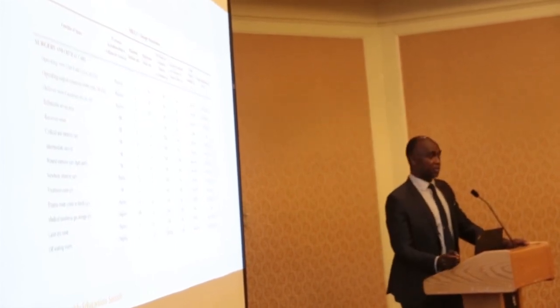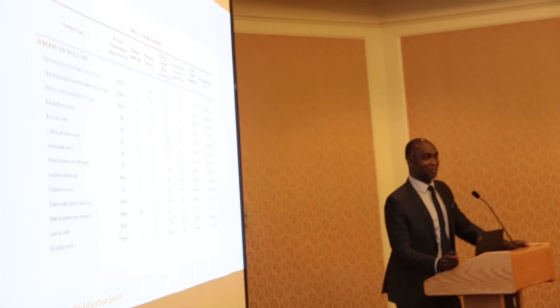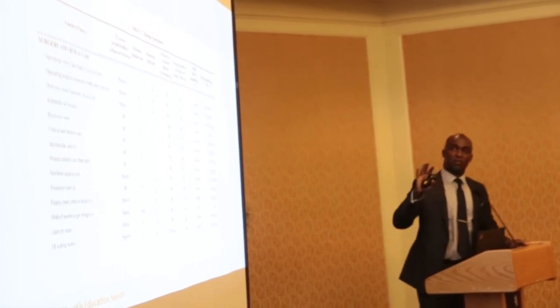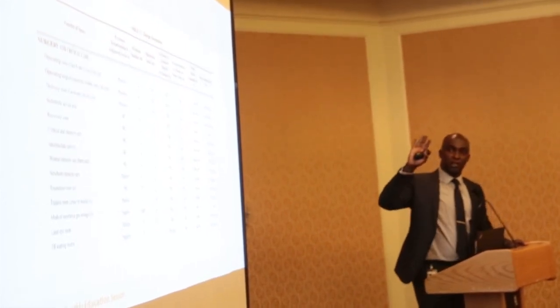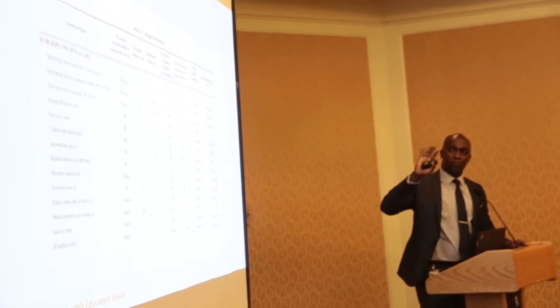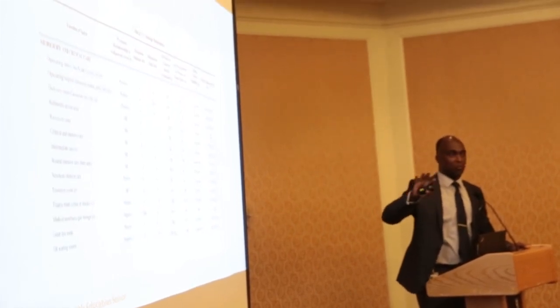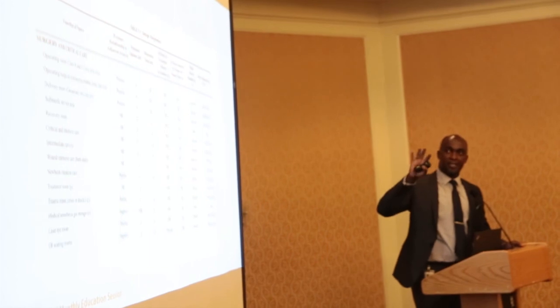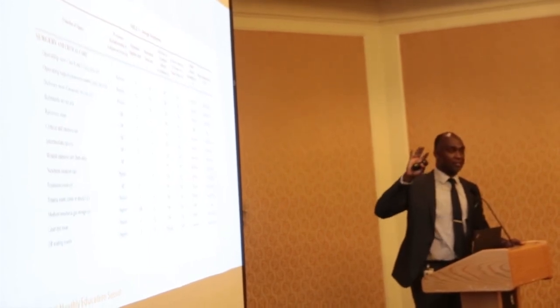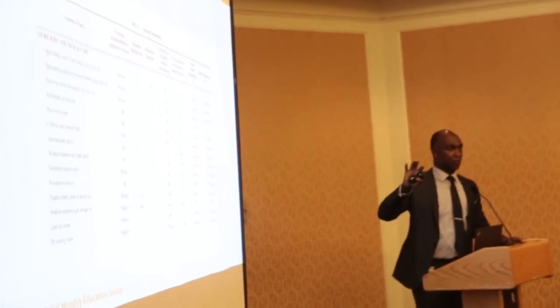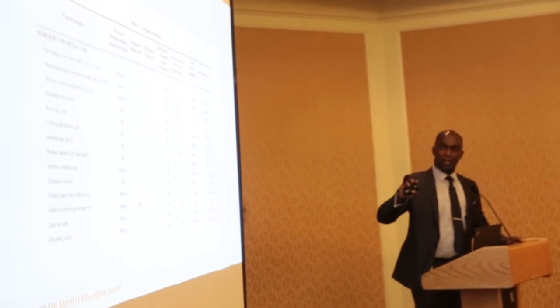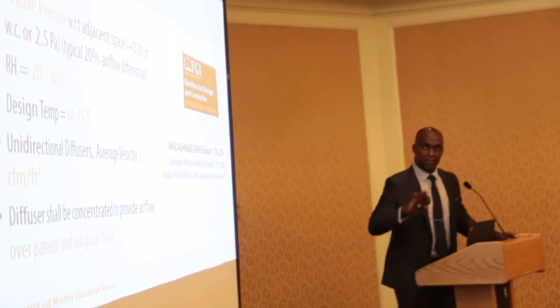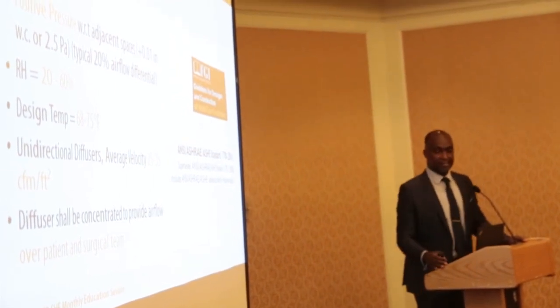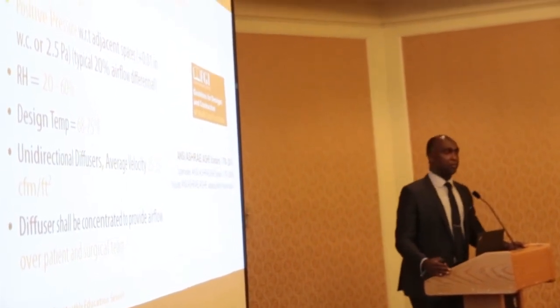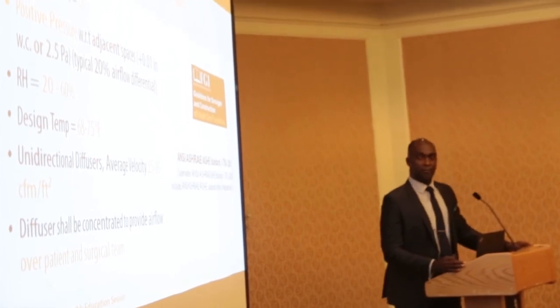I don't expect you to read this table, but it shows the guidelines required for all healthcare rooms within a hospital - it's table 7.1. This is the Bible for all engineers, and this is what we use. I'll show you the conditions defined by the table: it says that in an OR you have to have a minimum air change of 20.